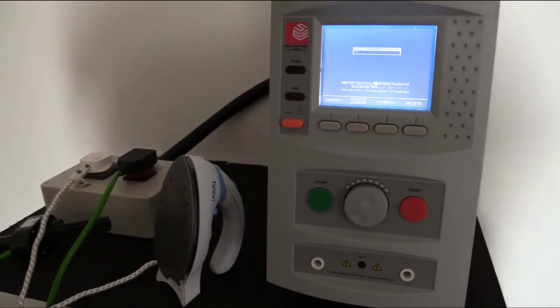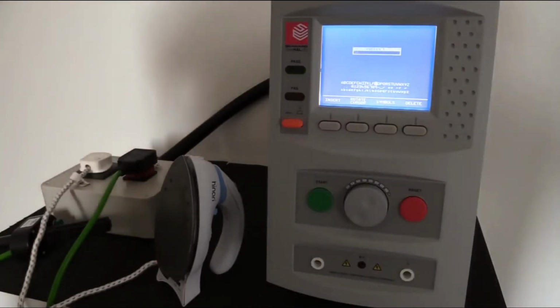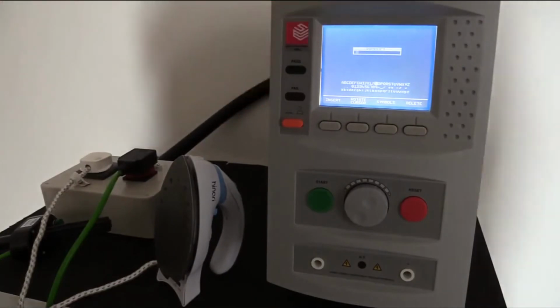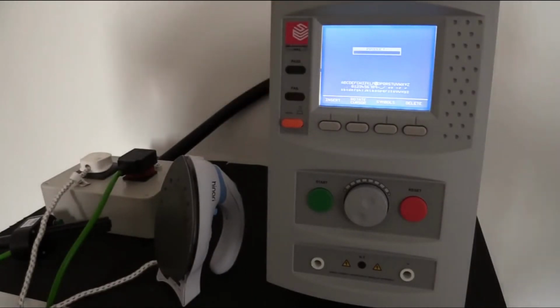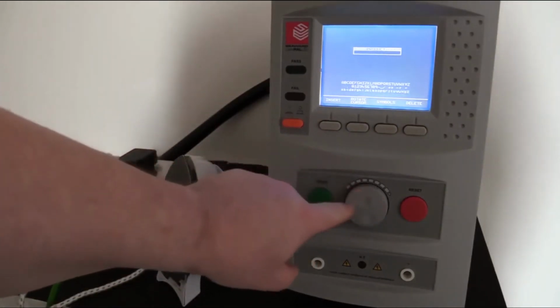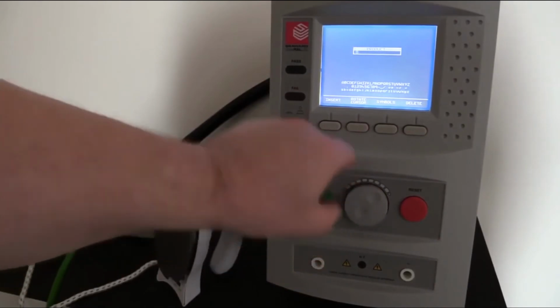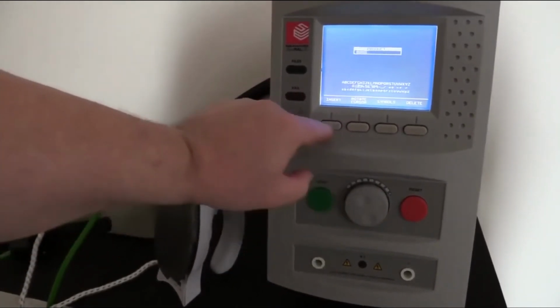So we're going to run through the test sequence we previously created. At the moment you'll see the HAL is ready to accept some data in order to create the test record for this particular product. At this stage it's prompting us to put in a unique reference number that relates to the item under test. Typically this would be a serial number. If your serial number is a barcode, the HAL can accept the barcode scanner, so we could simply scan the serial number. But just for demonstration purposes, let's put a number in.